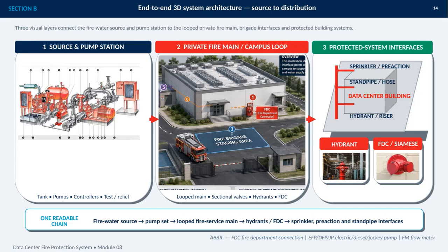This slide presents the end-to-end architecture as one connected fire protection chain, moving from the water source to the systems inside the data center. The key idea is continuity. Every layer has a defined role, and each handoff must remain clear and reliable. The first layer is the source and pump station, including the tank, pumps, controllers, and test or relief functions. From there, water enters the private fire main, or campus loop.